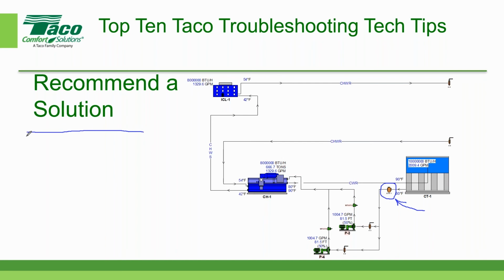It could have been. The point here is that once we narrow things down to where the problem was, in this case the basket strainer, then we're done. As far as TACO is concerned, we've helped the customer identify where the problem is. It's now up to them to sort out their basket strainer, because it has nothing to do with the pump. So unlike the original conclusion, that there's a problem with the pump, it turns out there was not a problem with the pump. It's actually a system issue, and in this particular case, it happened to be a basket strainer.